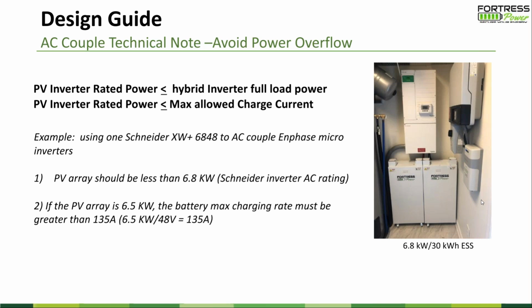We try to avoid it. The design note on this: we always want to design the energy storage part bigger than the PV side. For example, if a PV inverter is 5K, I will definitely design the energy storage inverter 5K or above, leave 10% on it. I try to use 6K because it can take more power and is more tolerable in the system. It becomes a buffer, especially with lithium battery.